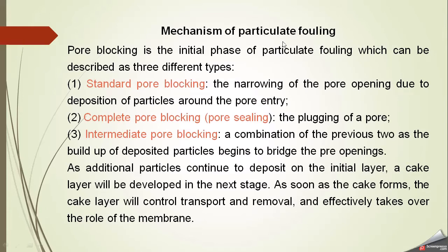The mechanism of particulate fouling begins with pore blocking, where particles settle and fix in the pores. There are three types of pore blocking. Standard pore blocking: narrowing the pore opening due to deposition of particles around the pore entry, reducing the pore size. Complete pore blocking (pore sealing): a particle of the same size as the membrane pore sits in and completely plugs the pore.